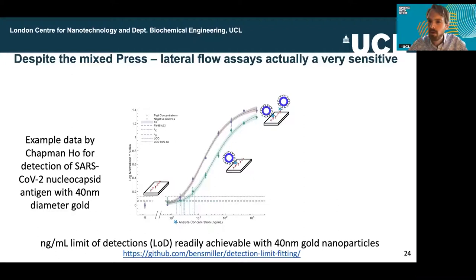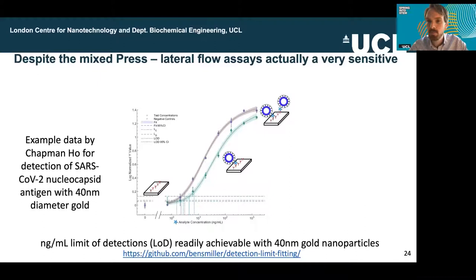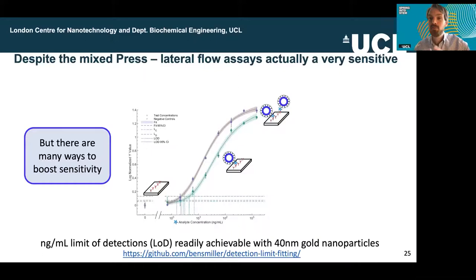Lateral flow tests are actually pretty good. Here's some data produced by one of my students — looking at one of these dose-response curves. The assay took about 10 minutes and gives a limit of detection somewhere around tens of nanograms per mil. A nanogram per mil is a really low, vanishingly small concentration of protein. Yet you can simply create something on nitrocellulose — spotting antibodies on a paper membrane, making and functionalizing particles — creating a very sensitive test that operates very quickly. This is by virtue of understanding and creating a diagnostic device that works as well as it can, given our understanding of mass transport limitations and reaction kinetics in these assays.